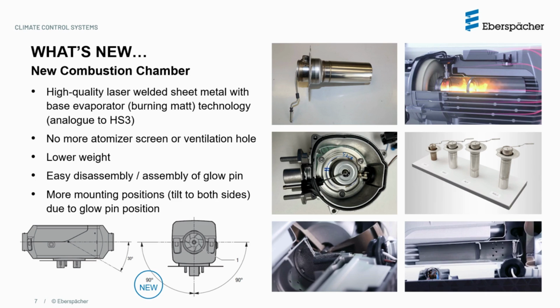One of the main differences is the new combustion chamber, similar to what you might have seen on the HS3, the third generation hydronic heater. It is made of high quality laser welded sheet metal with base evaporator, or in other words, a burning matte technology. It no longer has an atomizer screen or ventilation hole that requires maintenance like we had in the previous generations.